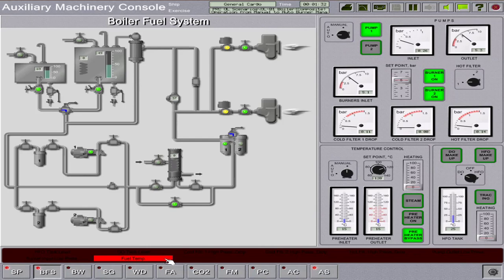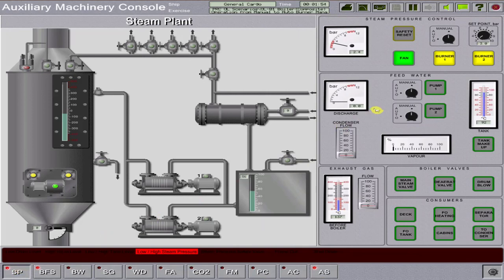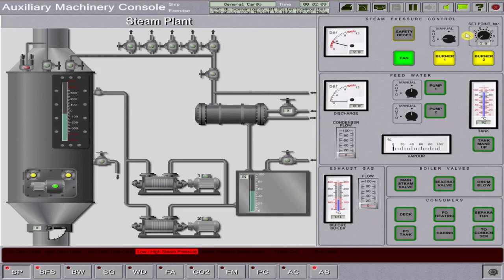This is normal because we are circulating diesel fuel oil in the boiler fuel system. You can see an icon indicating that the boiler is already running and burning diesel oil. Go back to the steam plant page and adjust the pressure set point to eight bars. First, you need to set the steam pressure controller to auto running condition, then set the set point to a maximum of eight bars.